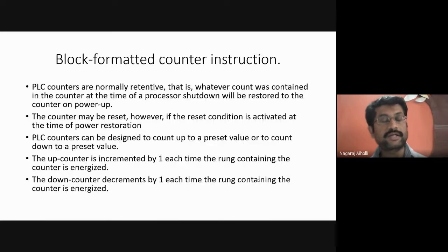This is an important point. PLC counters are normally retentive. That is, whatever count was contained in the counter at the time of processor shutdown, that means when the power supply is off, will be retained. That will not become zero. It will be restored to the counter on power up. Suppose the power supply goes off; you might expect the counter value to become 0, but it will not. Even after you turn on the power supply, the counter value will be maintained.